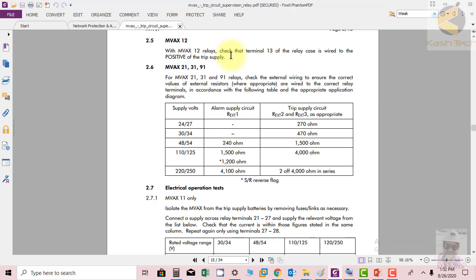For the MVAX 12 relay, check that terminal 13 of the relay case is wired to the positive of the trip supply. Then MVAX 21, 31, 91 - here you can see that you can connect different types of resistors.